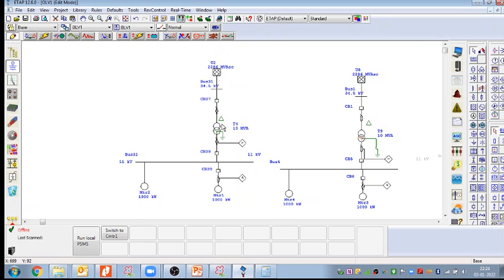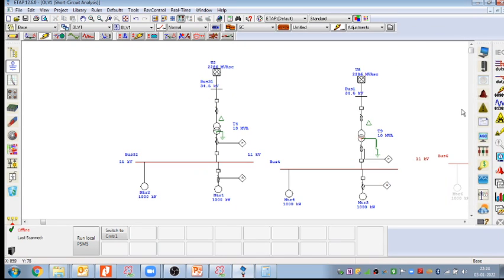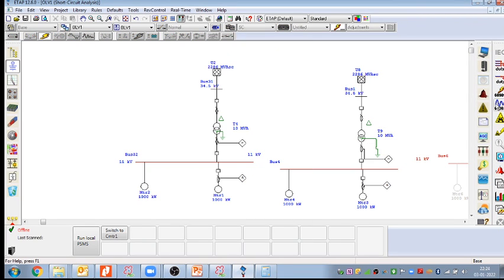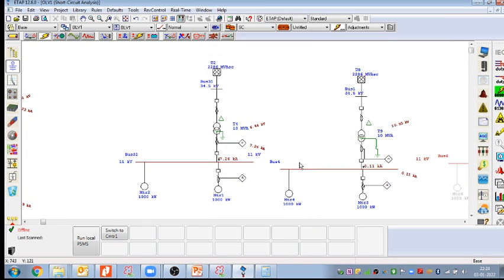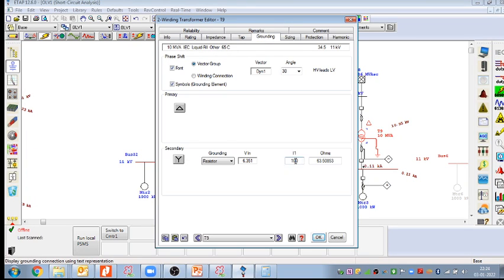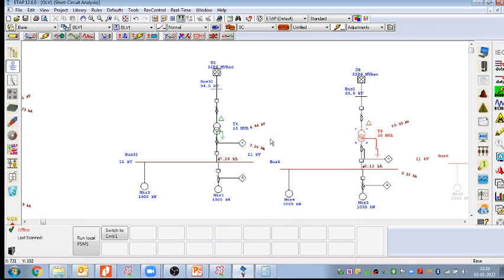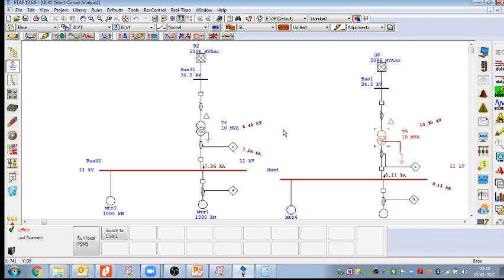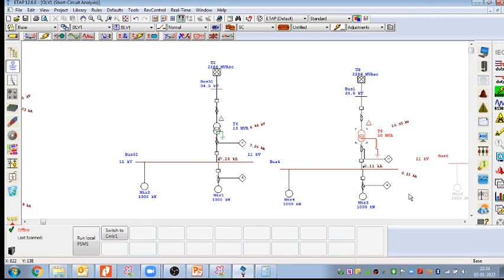Now let us compare solid grounding and NGR grounding. If I select and do the line to ground fault, let me do the 60909, and then the line to ground fault, let me run. What I can see here, how much current I wanted to limit is already clear. I wanted to limit 100 ampere only. So what will happen? What is happening here?